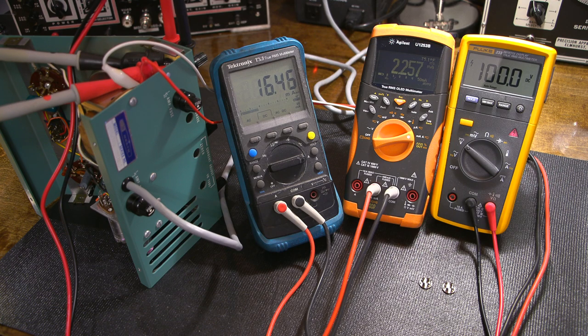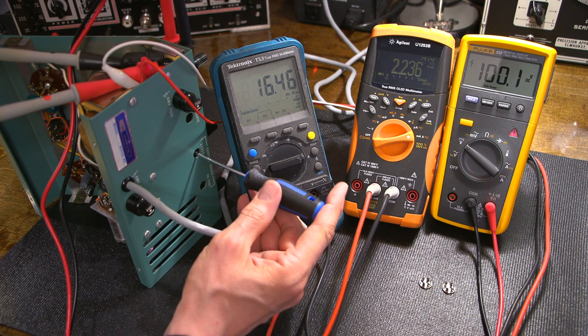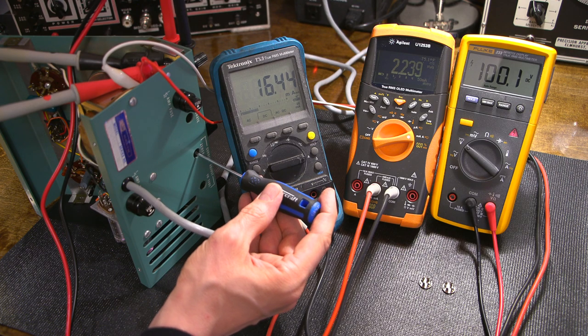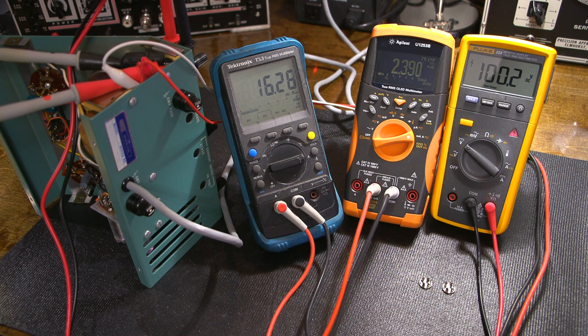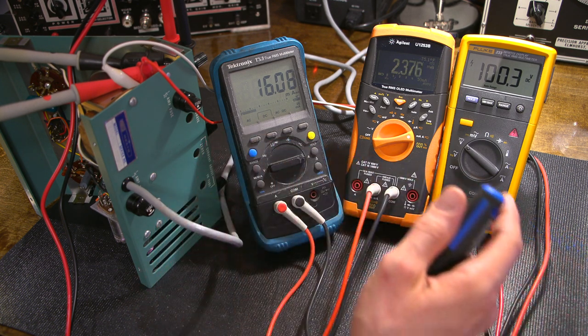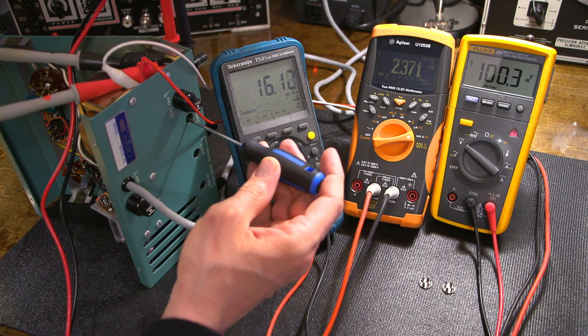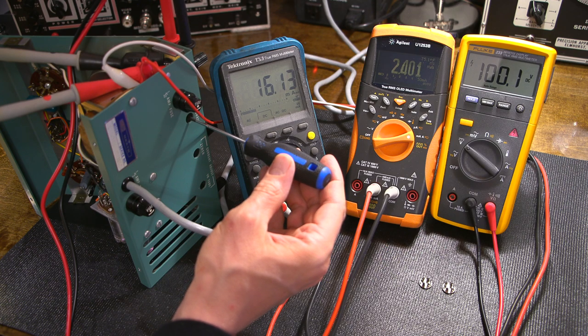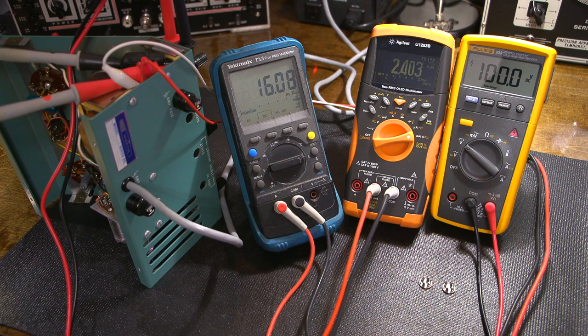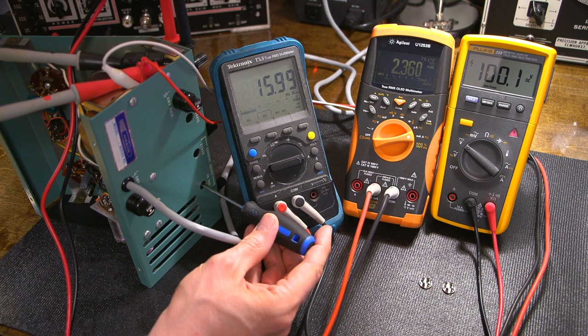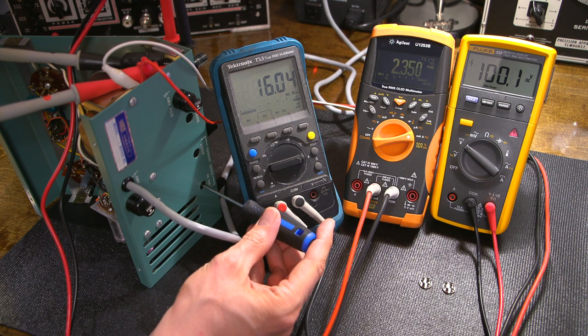It's not doing too bad. It's sitting at 2.2, it's supposed to be 2.3, right? It's creeping down, as you can see. So right now, again, I can spend a few moments here and just bump this up. Take that to 2.4. And as it warms up, it'll creep down again. And you can see as I bump that up, it changed the voltage here again, so I can move the calibration back down to 100.0 or close to. And it's at 2.4, so yeah, it's between 15 and 17 on the other end, 16. I'd prefer it to be about 16.5. So I can move the VR tube up just a little bit. Going to move at any rate.